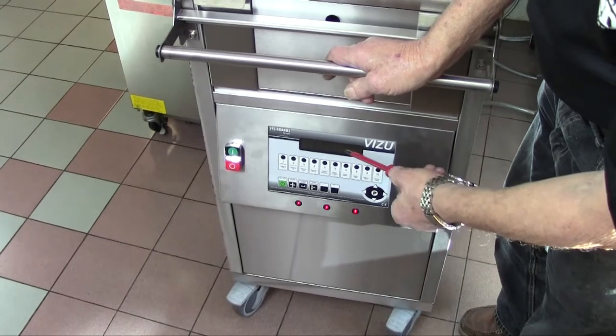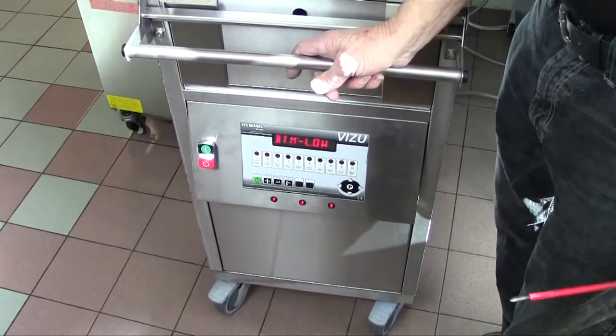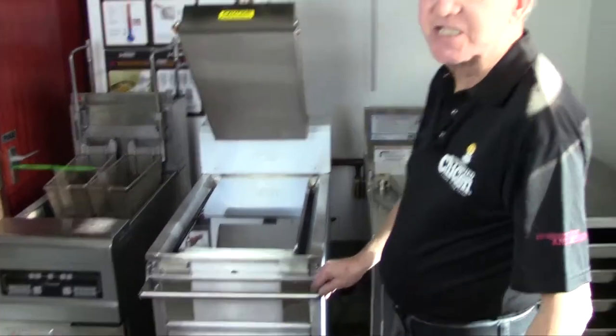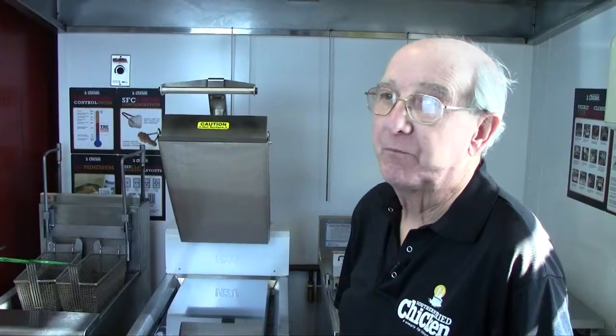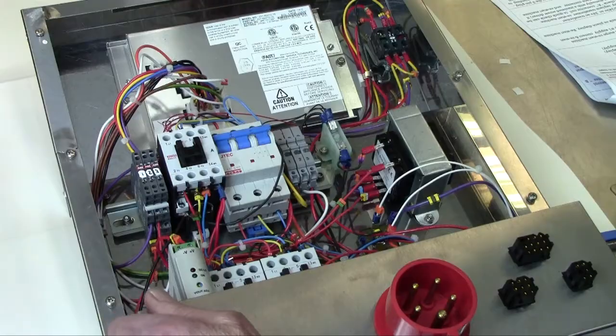If the machine starts, continue to start the machine and use it. If the high limit failed to reset, then replace the high limit stat. Before replacing the high limit stat, check the wiring to it and also check for continuity, as it could be a damaged wire or an open circuit.